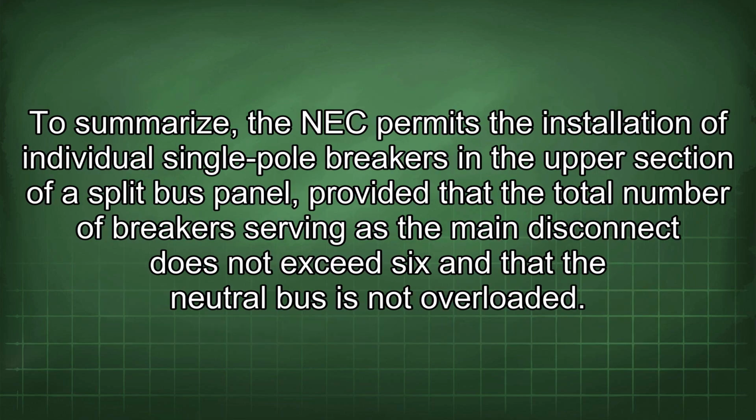To summarize, the NEC permits the installation of individual single-pole breakers in the upper section of a split bus panel, provided that the total number of breakers serving as the main disconnect does not exceed 6 and that the neutral bus is not overloaded.